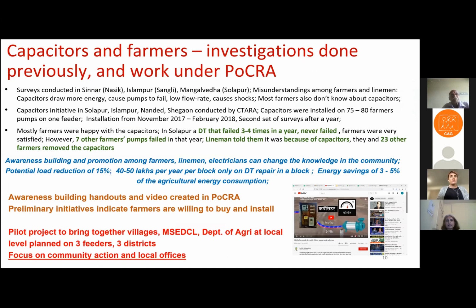Third, right now capacitor usage is almost non-existent, and the capacitor is an extremely low cost device - it costs a farmer only about 400 rupees. Once installed, it can last 5 to 10 years and can reduce the load by 10 to 20%. That's huge - important for farmers, and important for MSEDCL too, not just for transformer failure but even upstream. Improving the power factor, which is what the capacitor does, is very important for MSEDCL all around, and all it needs is awareness building with farmers.